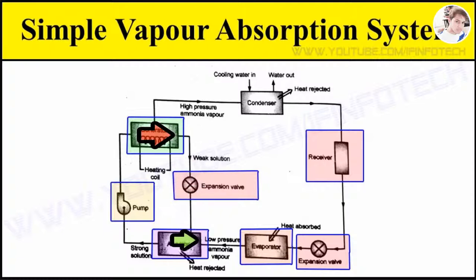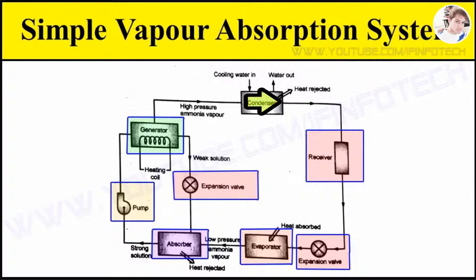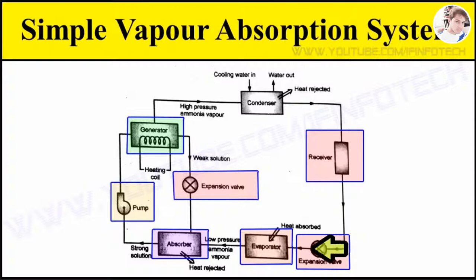The weak solution flows back to the absorber at low pressure after passing through the expansion valve. The high-pressure ammonia vapor from the generator is condensed in the condenser to high-pressure liquid ammonia. This liquid ammonia is passed through the expansion valve and receiver, and then to the evaporator, completing the simple vapor absorption cycle.